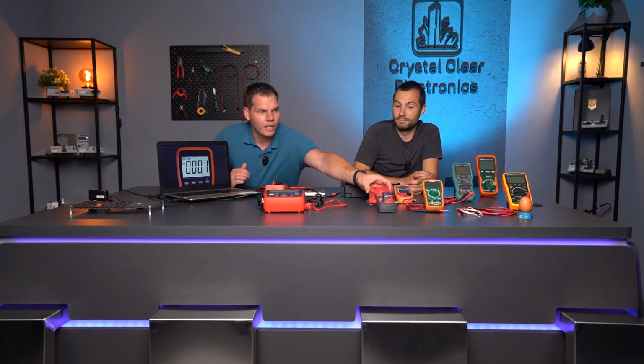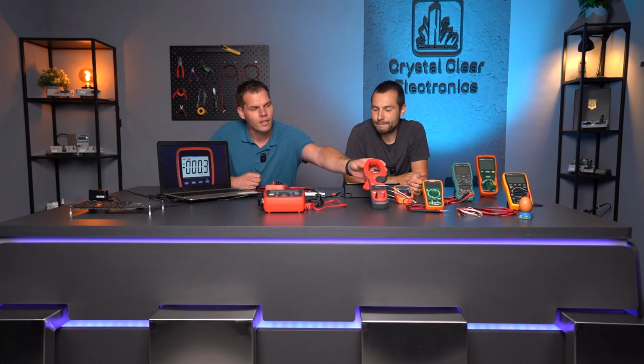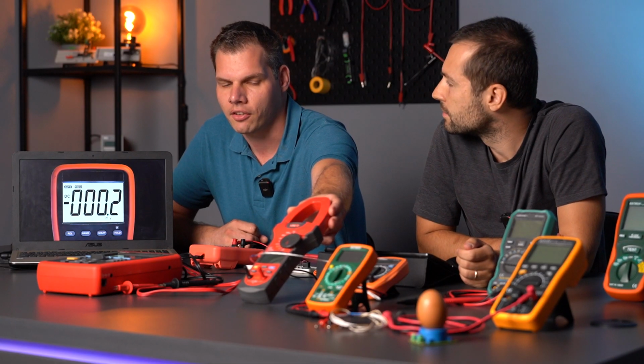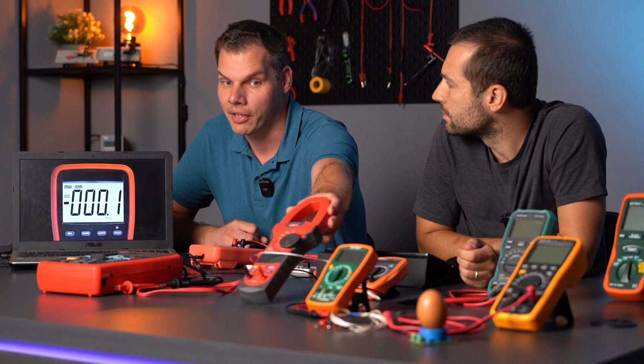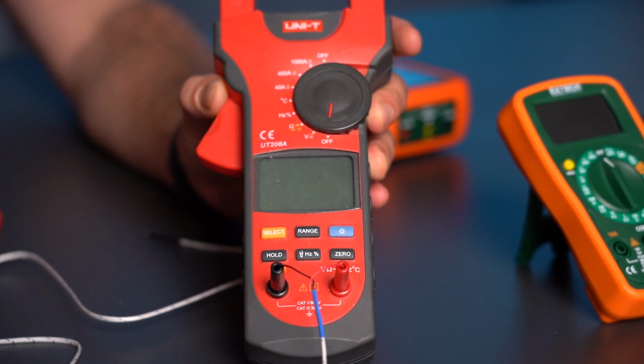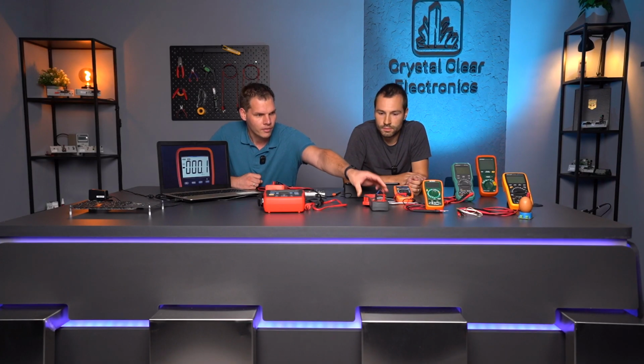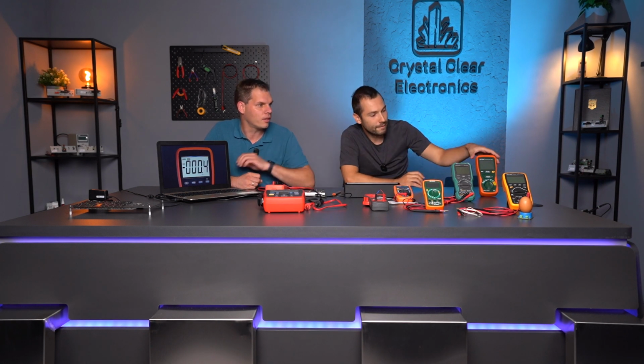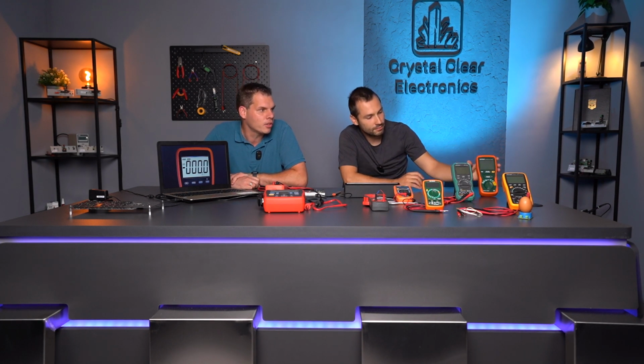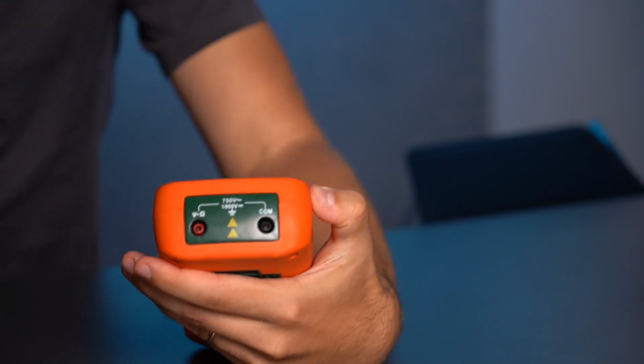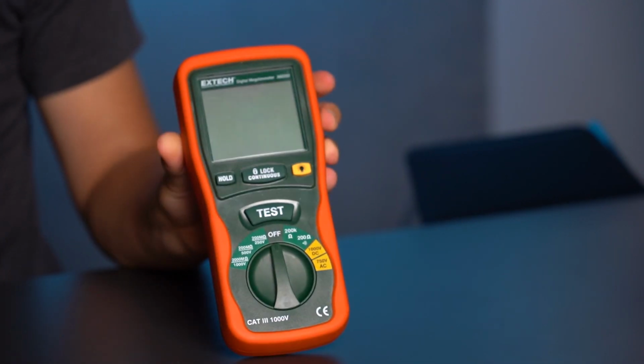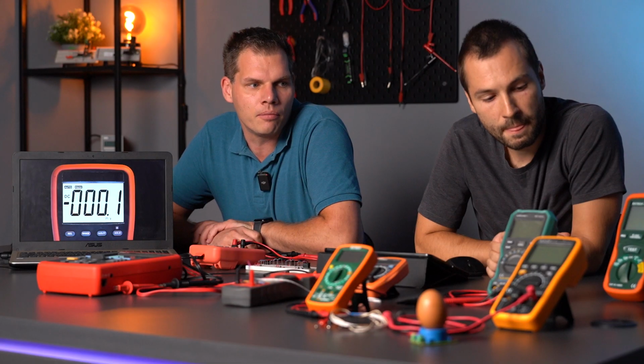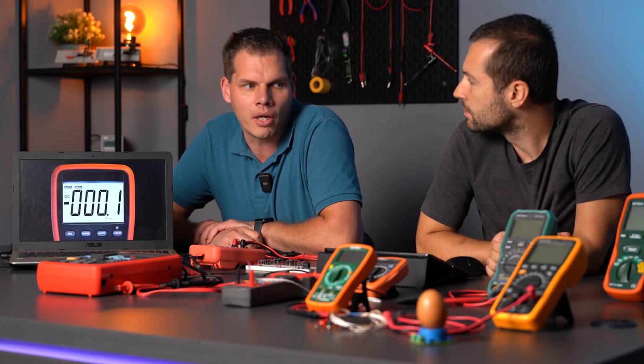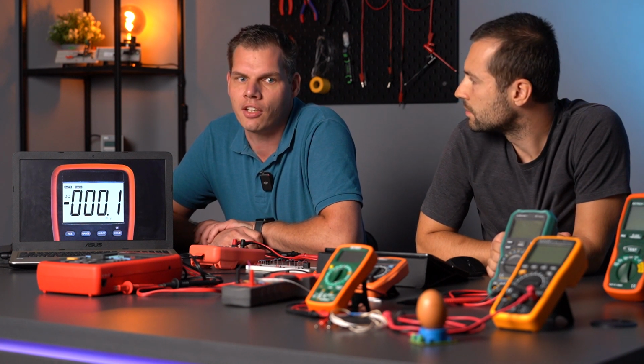Our next tool is a clamp meter. This is a good tool because it allows you to measure current without breaking the circuit. Our third and final tool is a megohm meter, which Béla will show you in a moment. This instrument is mainly used to measure the resistance of insulations in the range of many hundreds of kiloohms to megaohms.